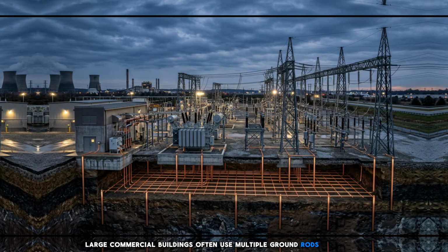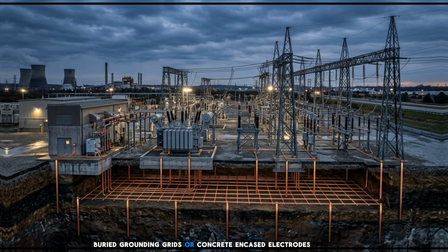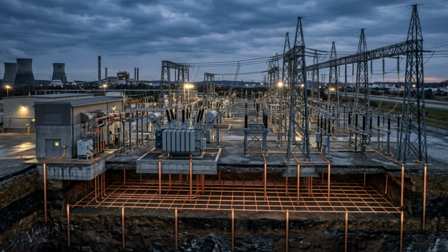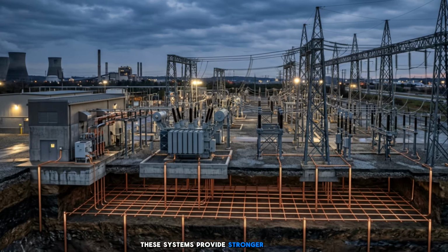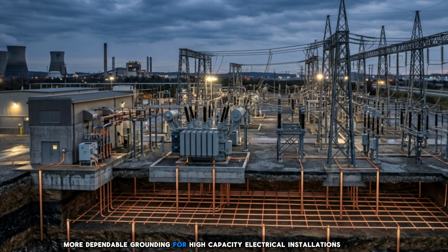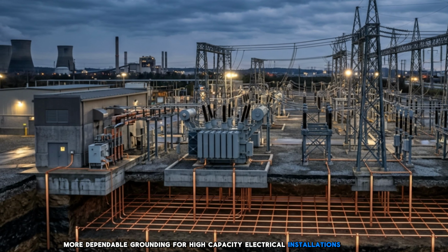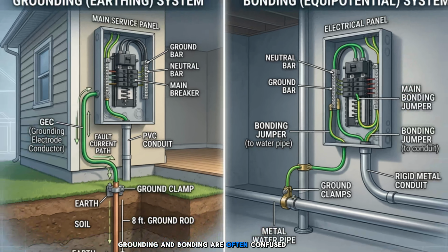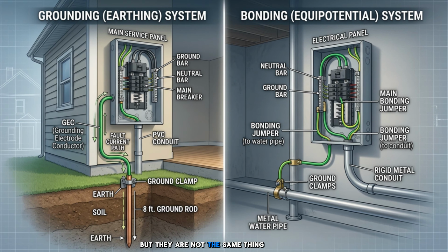Large commercial buildings often use multiple ground rods, buried grounding grids, or concrete-encased electrodes. These systems provide stronger, more dependable grounding for high-capacity electrical installations. Grounding and bonding are often confused. But they are not the same thing.